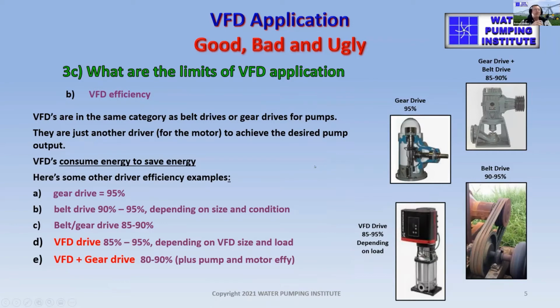So VFDs come in the same categories as belt drives or gear drives. It's just another driver. A gear drive is 95%. A belt drive is probably 93%. So a belt drive and a gear drive is between 80 and 90%. A VF drive is between 85 and 95, depending on the VFD size. Those lower numbers would be associated with 1 or 2 horsepower. They're very, very inefficient. If you put a VFD on a gear drive, you'd definitely be below 90% on drive efficiency. So those things need to be taken into account when we assess what our final savings are going to be.